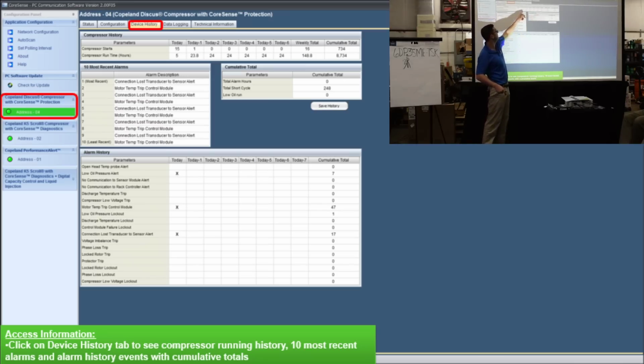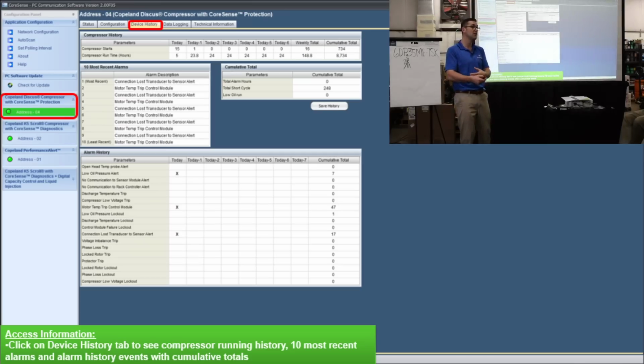Now, all of a sudden it started to stop running. And look at this, low oil pressure, 7 times. Right, so now it's telling me. If you came up to a system and you didn't have this, you're going to search for a little while, start the compressor up and try to figure out, hopefully check your net oil pressure, and then you'll learn. But right here, right off the bat, there's something going on with the oil.